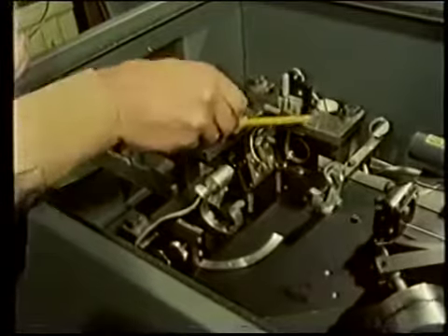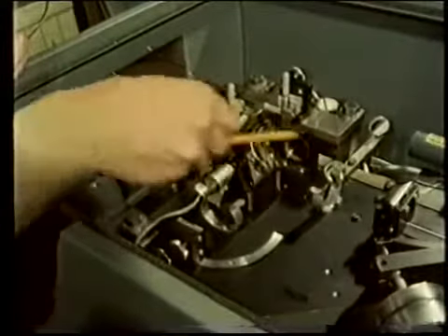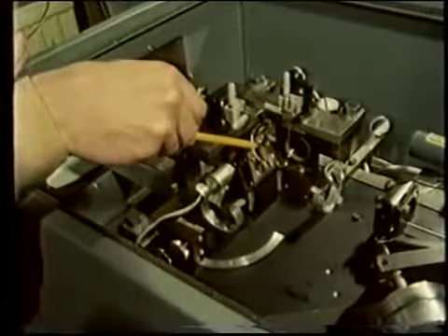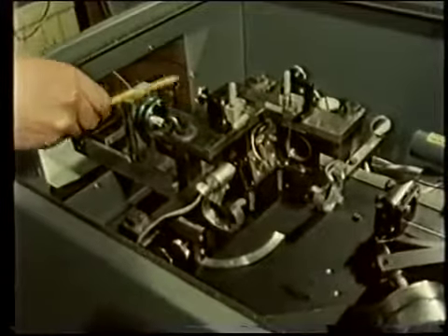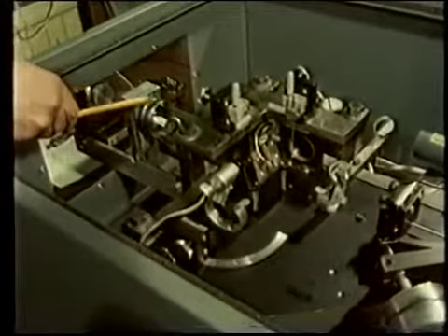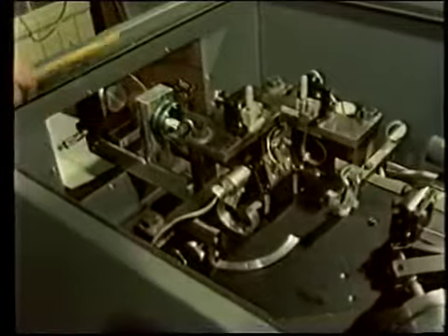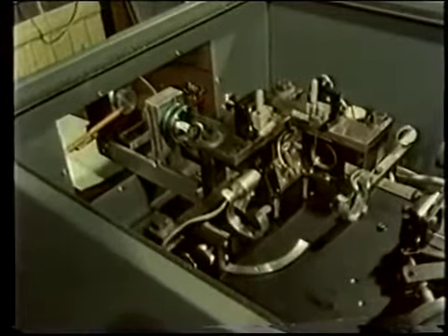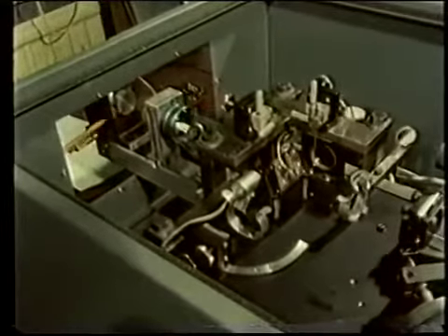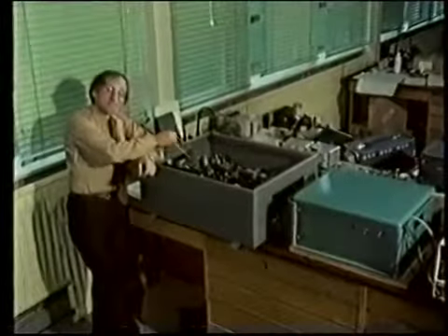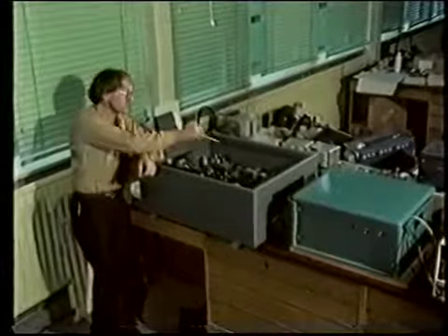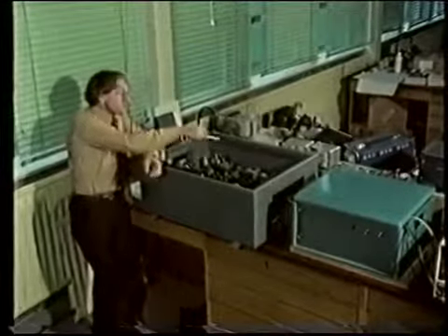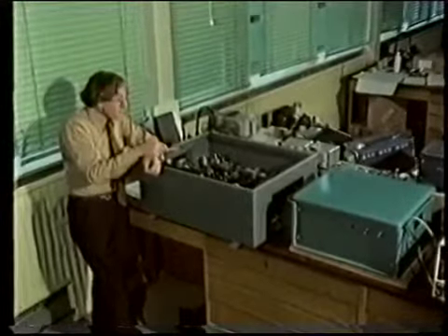After the collimated radiation passes in the usual ways through the system, it comes down here, passes through our sample cell, and so to a radiation detector. Why, you may say, do we place the sample cell here next to the detector? Why don't we place it, say, immediately beyond the source?